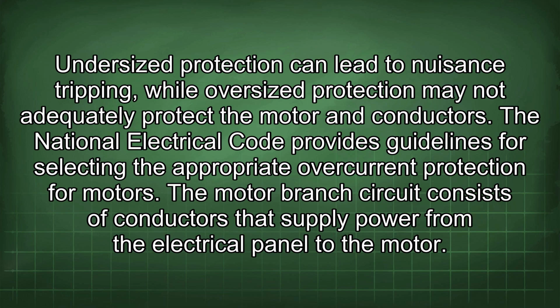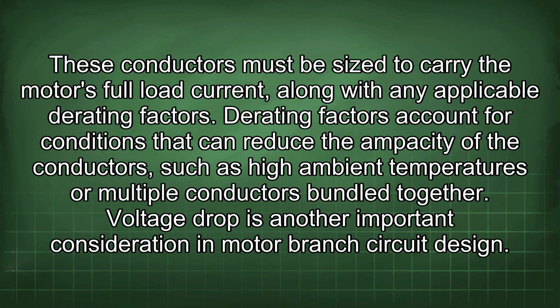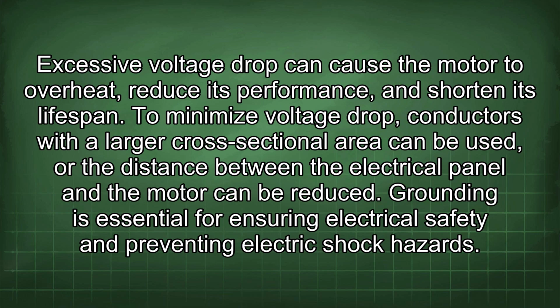The motor branch circuit consists of conductors that supply power from the electrical panel to the motor. These conductors must be sized to carry the motor's full load current, along with any applicable derating factors. Derating factors account for conditions that can reduce the ampacity of the conductors, such as high ambient temperatures or multiple conductors bundled together. Voltage drop is another important consideration in motor branch circuit design. Excessive voltage drop can cause the motor to overheat, reduce its performance, and shorten its lifespan. To minimize voltage drop, conductors with a larger cross-sectional area can be used, or the distance between the electrical panel and the motor can be reduced.